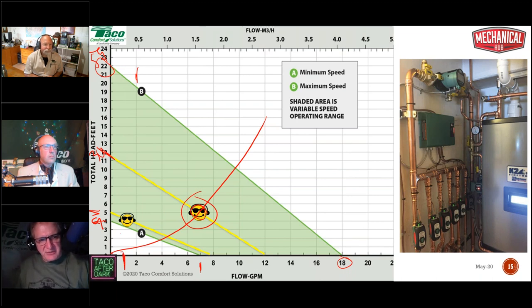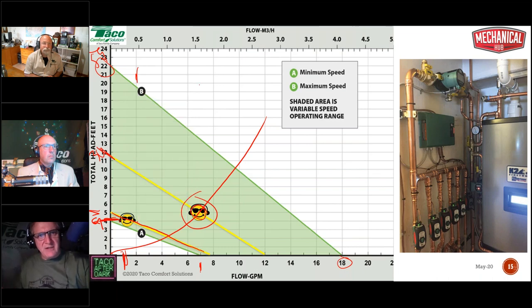Now, this line represents the single smallest zone, 1 gallon a minute at 4 feet of head. So it's going to operate on that line with that one zone calling. As zones open, the delta T on that system is naturally going to want to get a little wider, because we're taking more energy out of the fluid. The sensors pick that up, the pump speeds up, and we go faster and faster until we hit our max. The pump sees a widening delta T as zones open and says, the delta T is getting wider, I better giddy up some, and it goes a little faster. When all zones are open, it should be operating right on this line under design conditions. As zones close, it does exactly the opposite and goes back down the other direction.